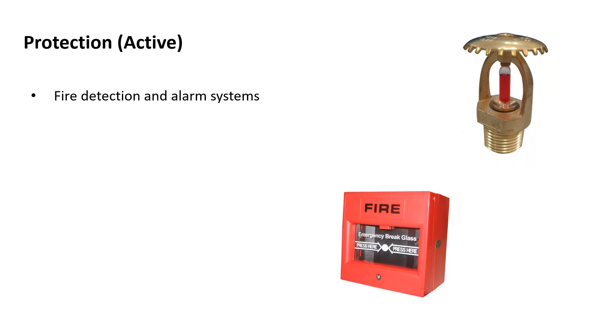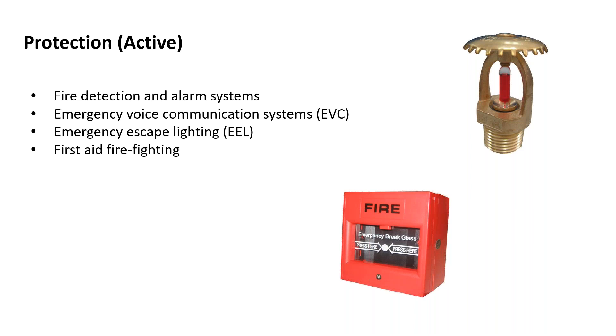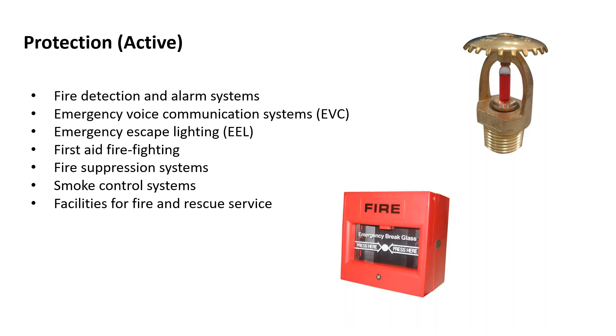PAS 79 also covers active protection measures: fire alarm systems and fire detection (from manual call points up to L1 category smoke detection everywhere), emergency voice communication systems (EVCs) if needed, emergency lighting, first aid firefighting equipment, fire suppression systems, smoke control systems, and facilities for the fire and rescue service.